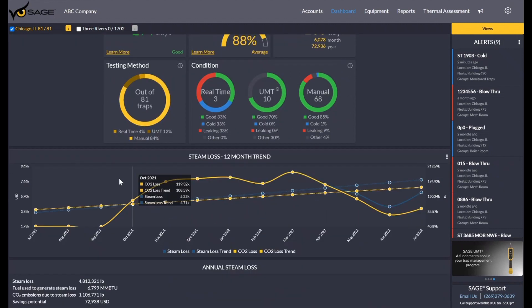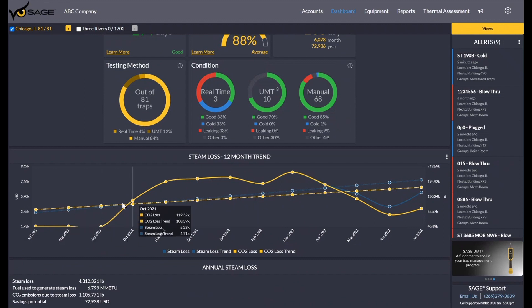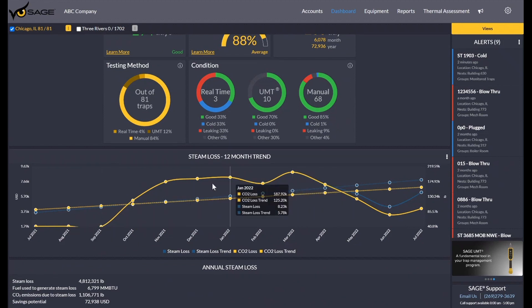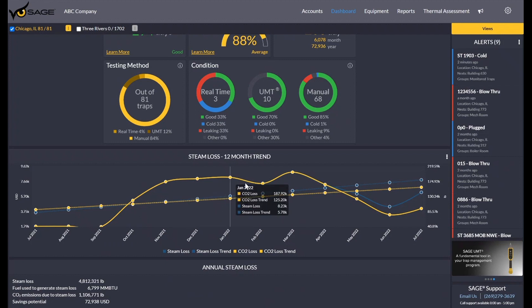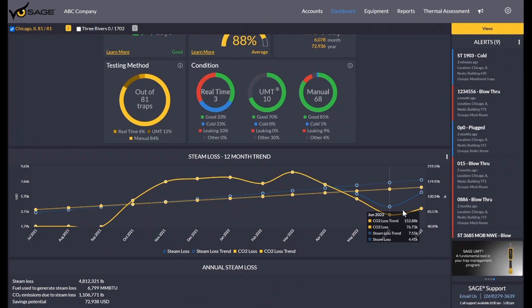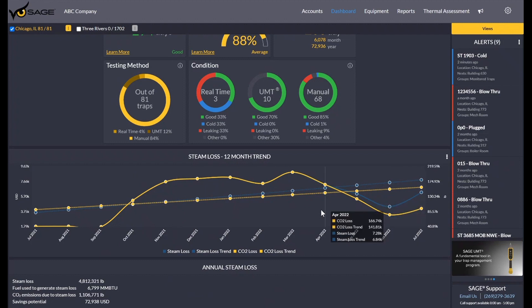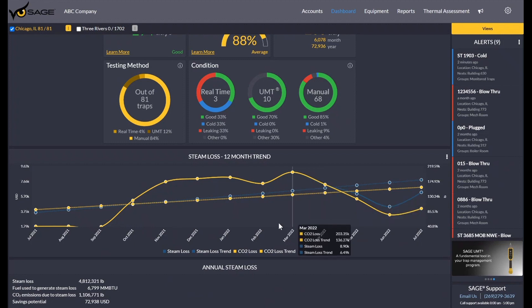As you can see below that, we have the steam loss trend chart, which kind of shows us how our system is performing over time and how it's trending. As you can see here, there was some initial losses found. They started to be taken care of, changed to good, and the losses were coming down. But now it looks like maybe there's some new failures cropping up in a newer survey, so we're starting to see the trend go back up.